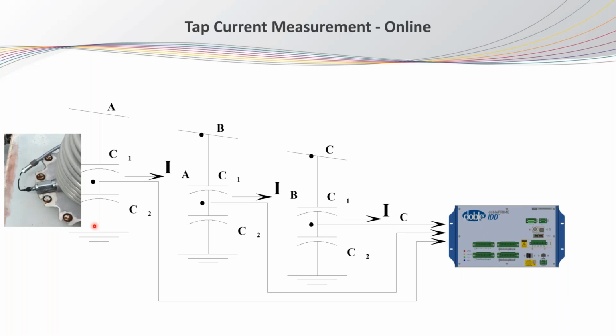So this slide is just to focus more on the power factor of the bushing and how to measure it online. Usually we measure the power factor of the transformer through offline testing. So the transformer is out of service, and then we apply a voltage on the bushing, and we measure the leakage current through the test tap.